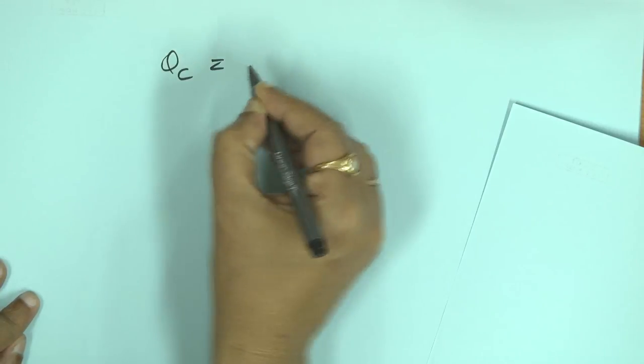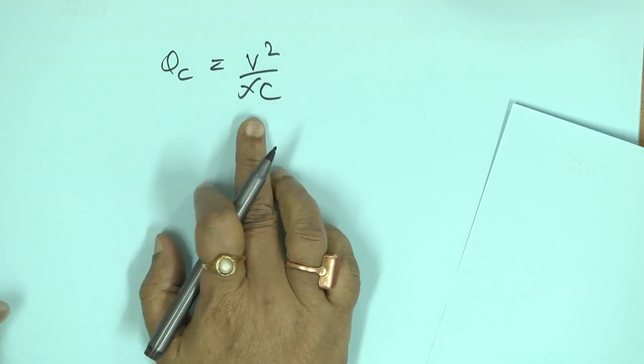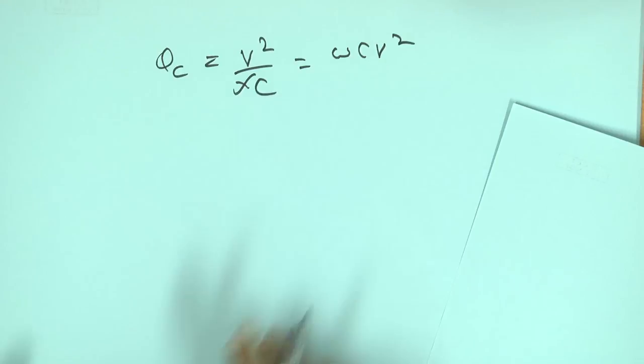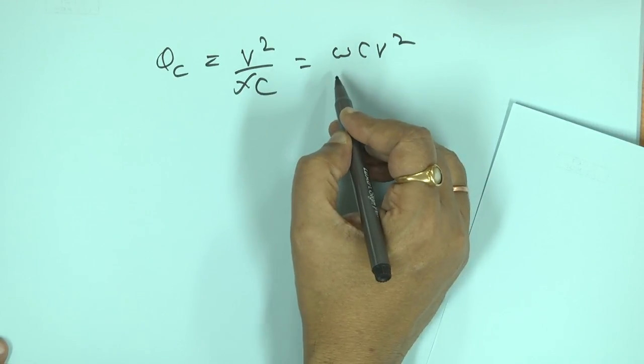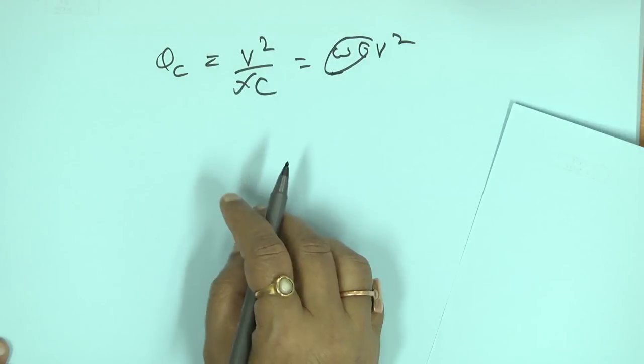So if suppose a 1 megawatt capacitor is given, meaning it is connected at say 11 kV voltage for example - 11 kV means 1 per unit. That means QC is proportional to V square, so you can write QC equals QC0 into V square. Something like this - I won't write it all out. So QC, if you write it like this, reactive power equals V square upon XC, where XC is 1 upon omega C. Basically it's omega C V square. But omega is 2 pi f, and assuming frequency is constant, XC is constant.